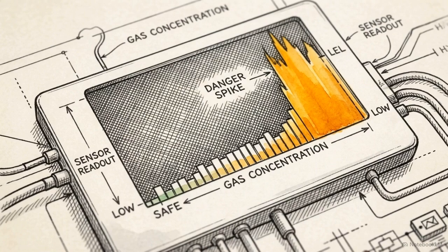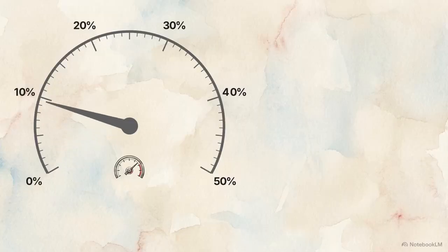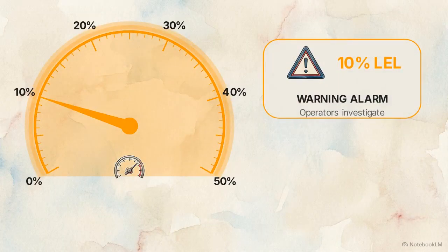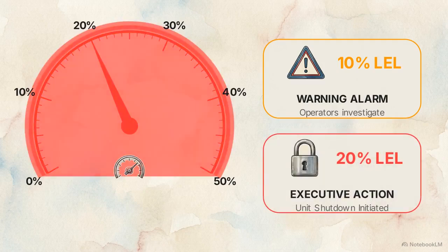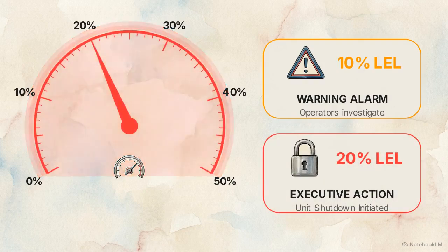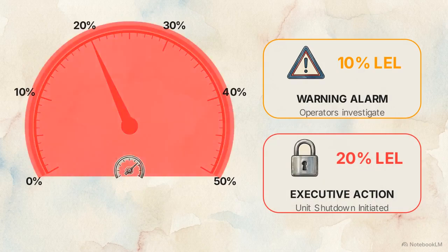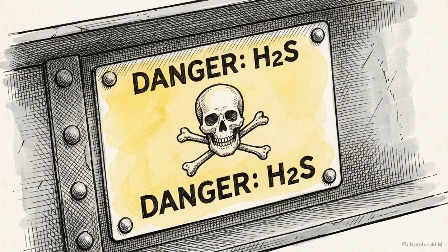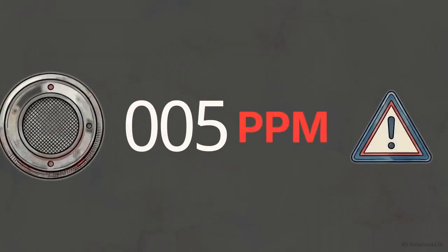Flammable gas concentration is measured as a percentage of its lower explosive limit, or LEL. Reaching 10% LEL triggers a warning alarm, requiring operators to investigate. Hitting 20% LEL triggers an automatic executive action, shutting down the unit. Toxic gases require a different scale. Hydrogen sulfide is lethal in tiny concentrations, so sensors measure it in precise parts per million, or ppm, triggering alarms at single-digit levels.